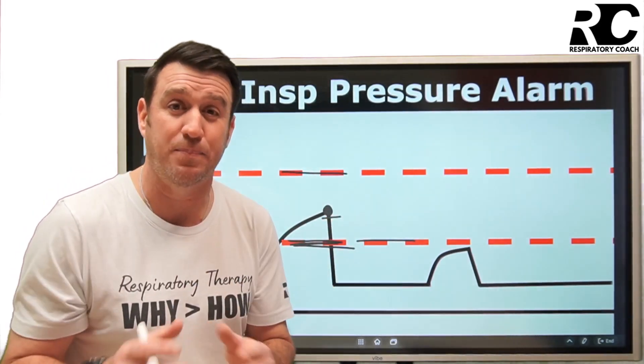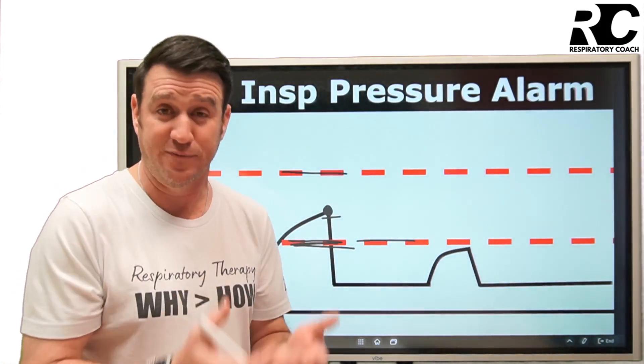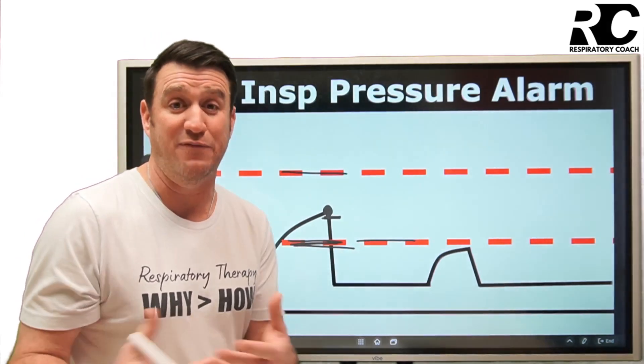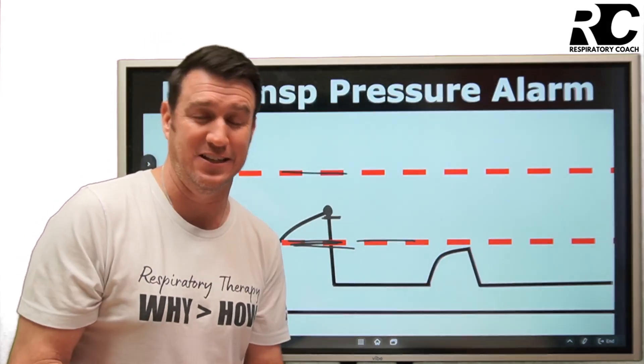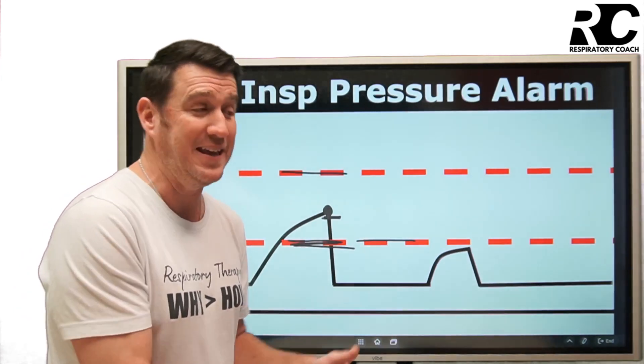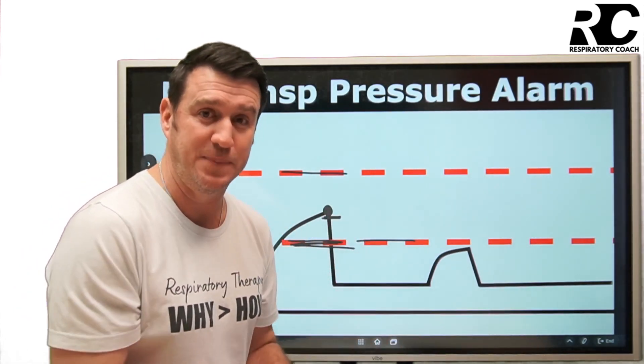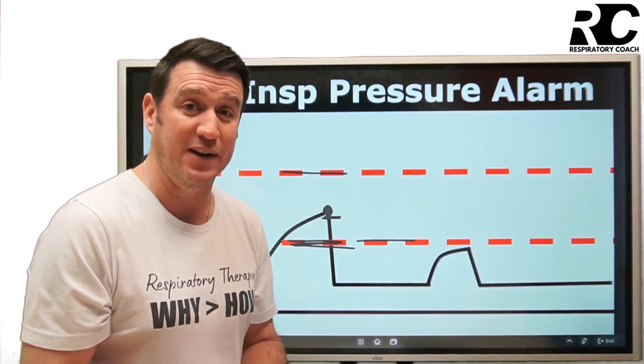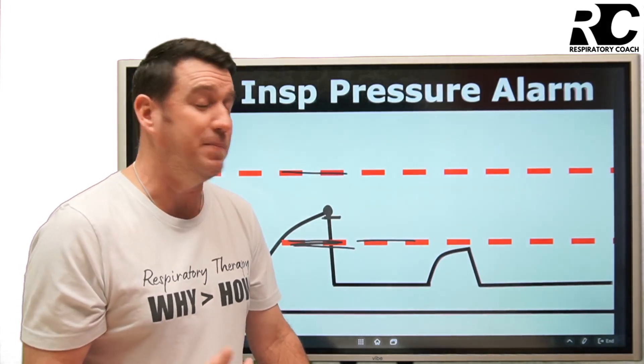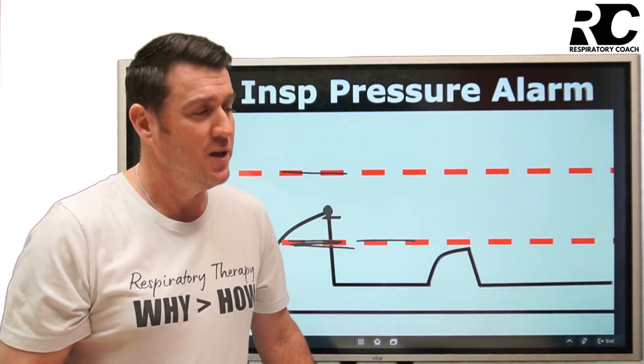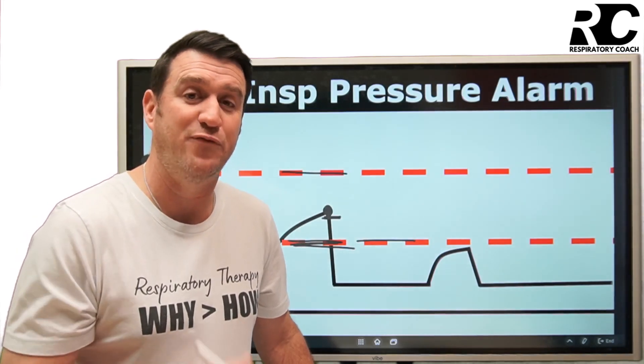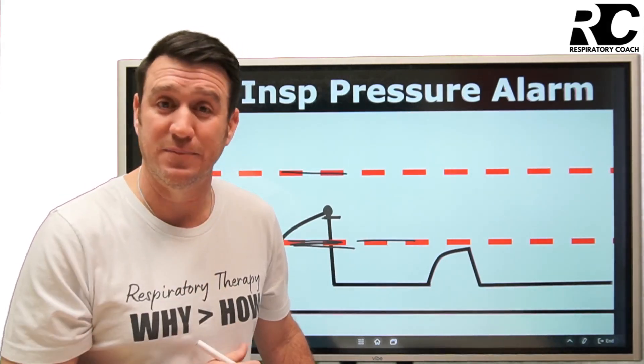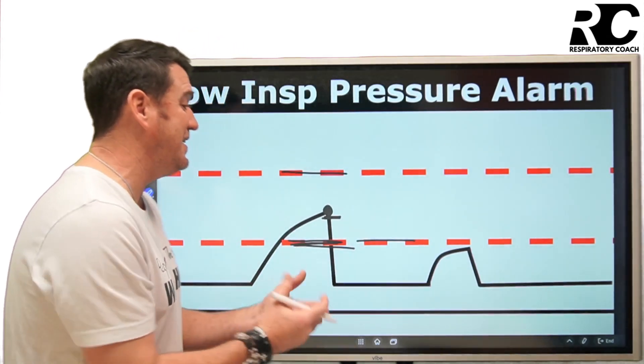You don't want the low inspiratory pressure alarm set too high, because small changes in pressure during volume control ventilation can cause fluctuations. It can't be set too close to your actual peak inspiratory pressure. Some say 5 cmH2O below, some say 10 cmH2O below your actual steady and stable peak inspiratory pressure. But it has to make sense for each patient — if a patient's PIP is 14 cmH2O, you'd probably set the alarm around 8 or 9 cmH2O rather than 4.